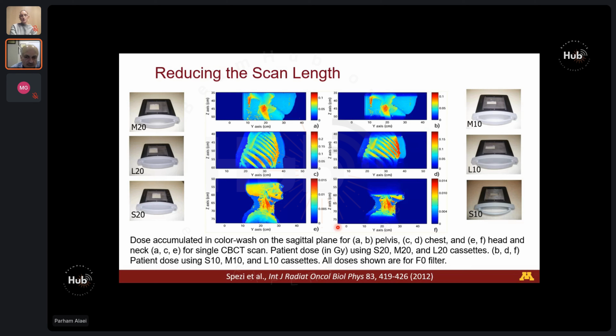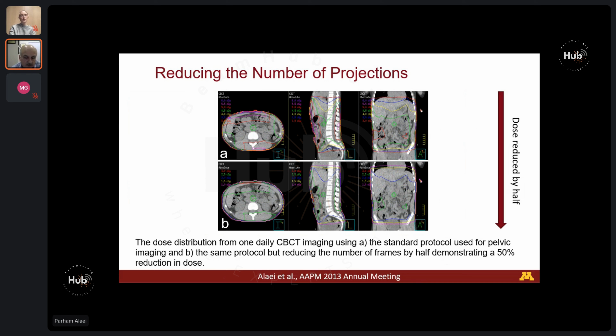Number of projections, again, this was a simulated study. This was on an actual patient, but again, the number of projections can be changed on the protocols. Say go from 900 to 450, and that cuts down the dose by 50%. And again, the dose variation, you can see it here, is a dose reduced by half, just simply by cutting the number of projections. Again, providing the image quality is adequate.